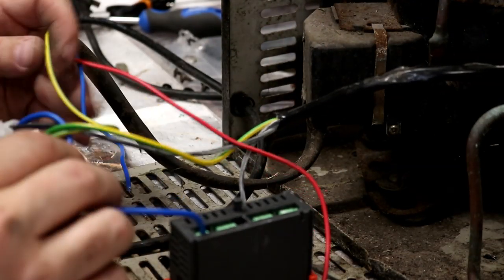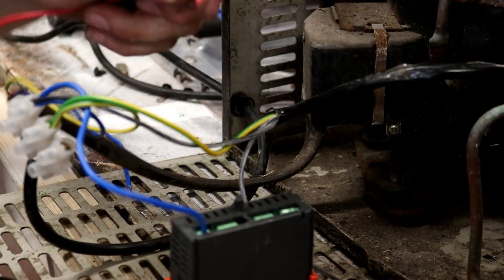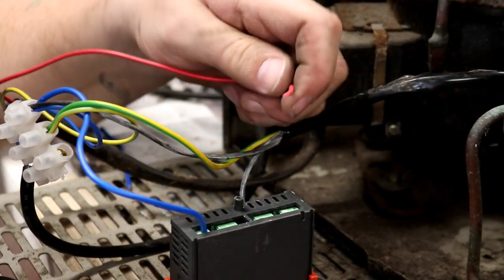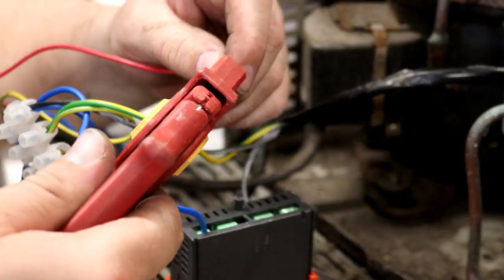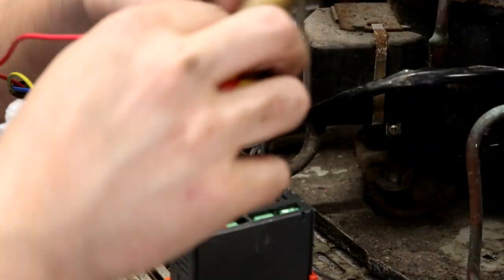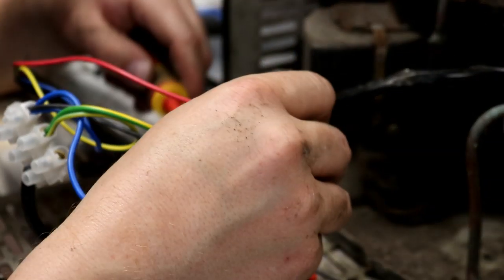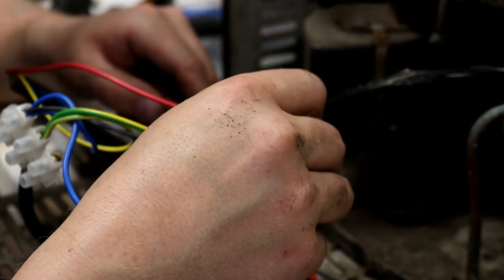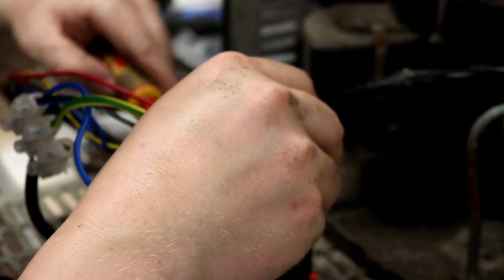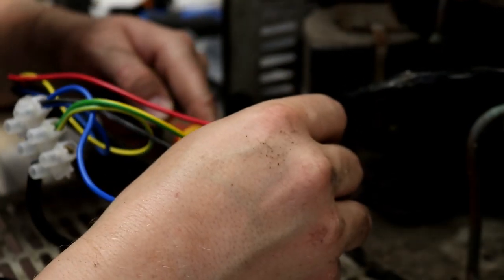Next, we need a live for the pump. So this is the live for the pump. We don't want to be putting that into the terminal block, but instead we want to put that on the relay output on the cooling side of the STC, which is just there.